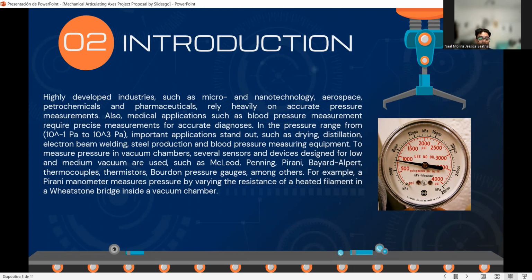To measure pressure in vacuum chambers, several sensors and devices designed for low and medium vacuum are used, such as McLeod, Penning, Pirani, Bayard-Alpert, thermocouples, thermistors, Bourdon pressure gauges, and others. For example, a Pirani manometer measures pressure by the variation of resistance of a heated filament in a Wheatstone bridge. Another example is the blood pressure manometer, used in hospitals by doctors, which is an essential instrument.